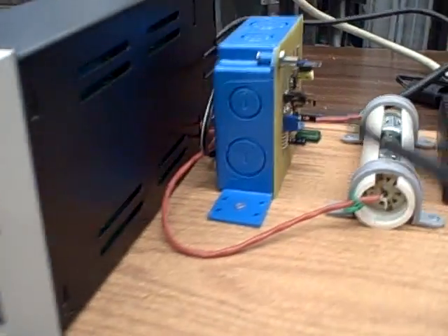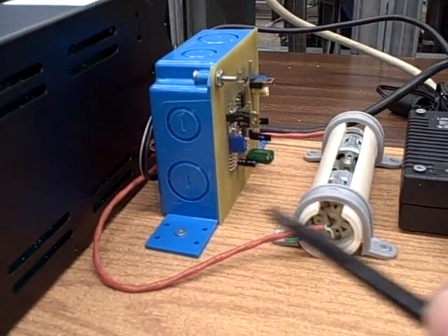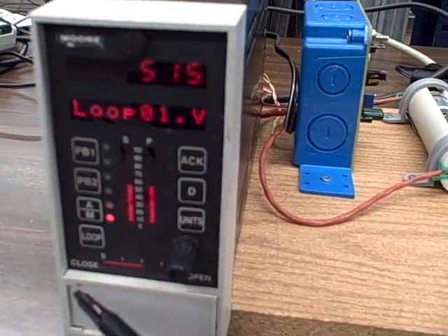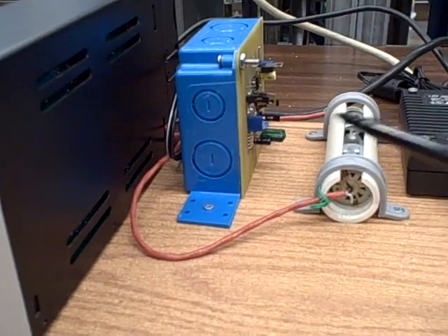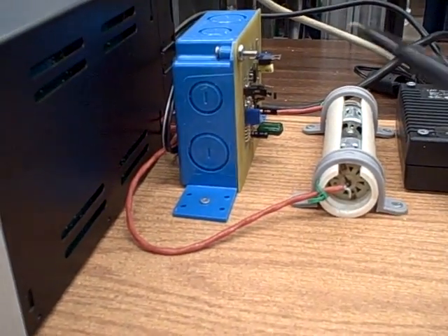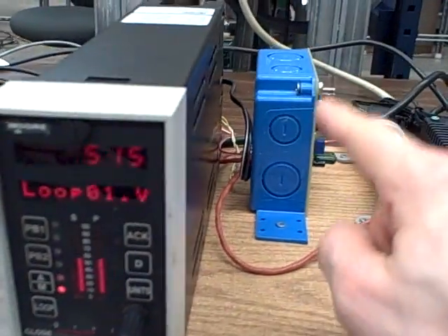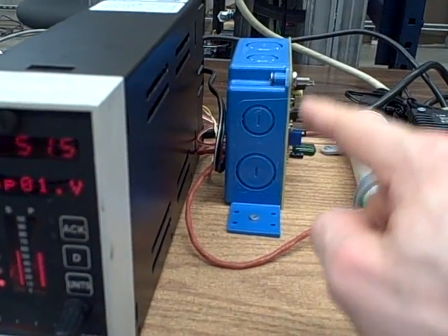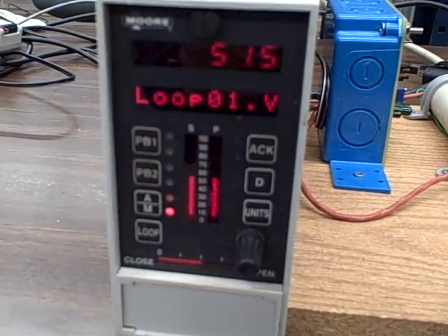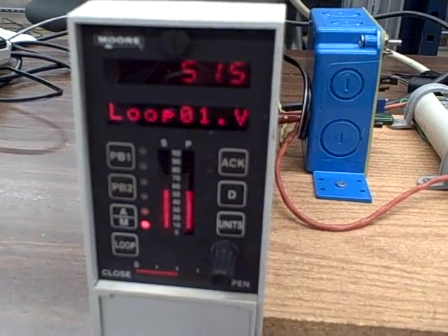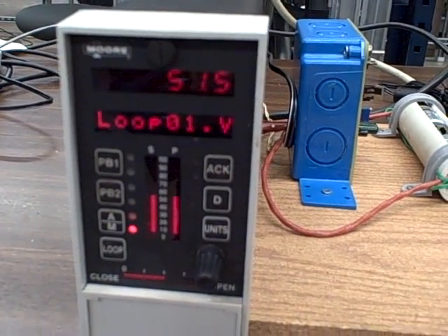That's because I've made the variable speed motor drive now a reverse acting unit. Less current signal to that variable speed motor drive makes more power go to the motor, makes it spin faster. So basically I've made my variable speed motor drive act backwards. This has profound effects when it comes to controlling automatically in automatic mode.